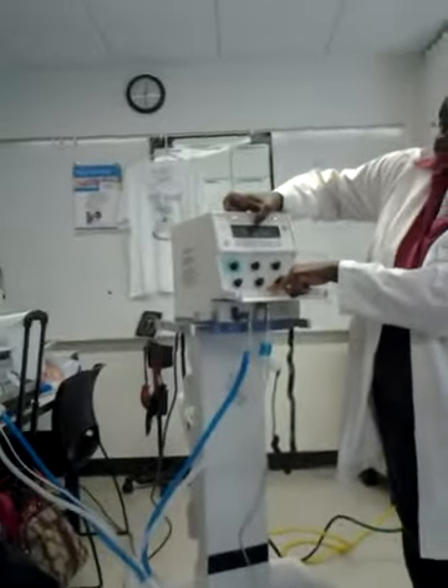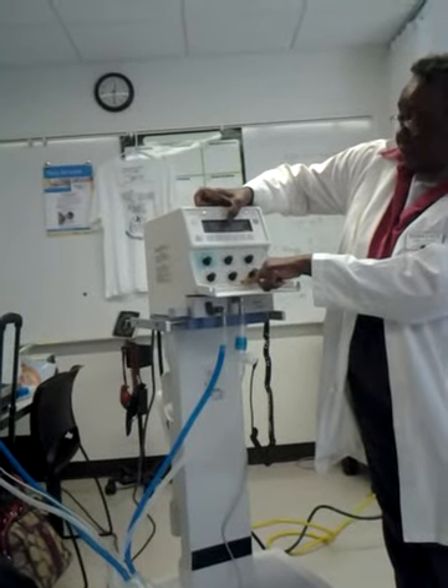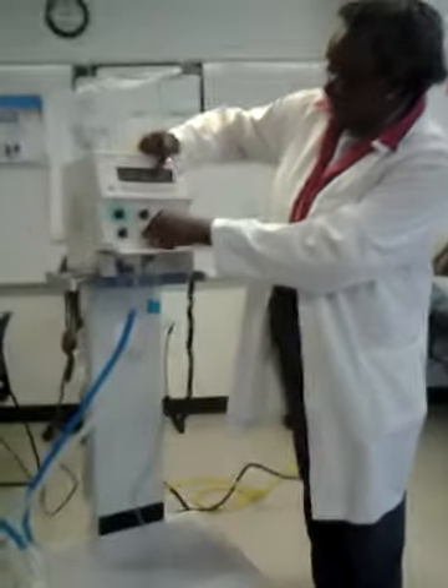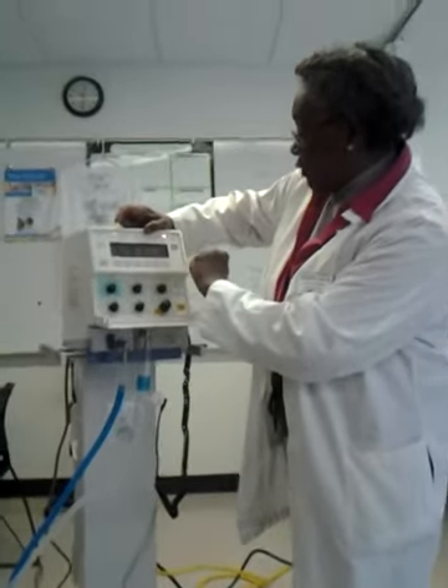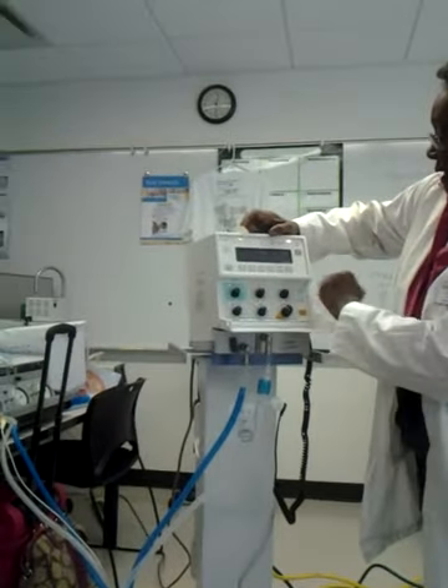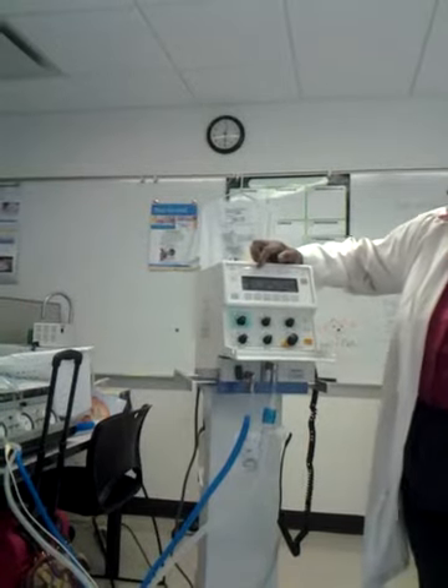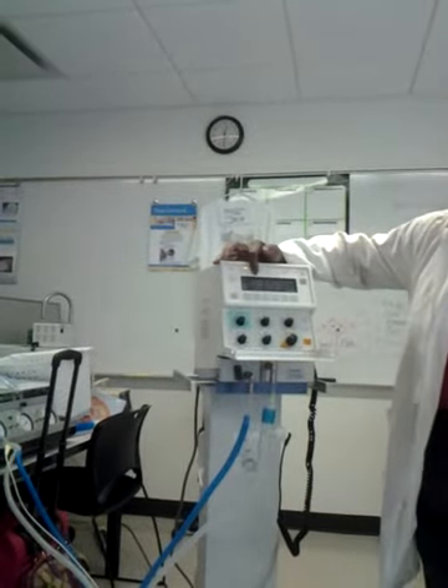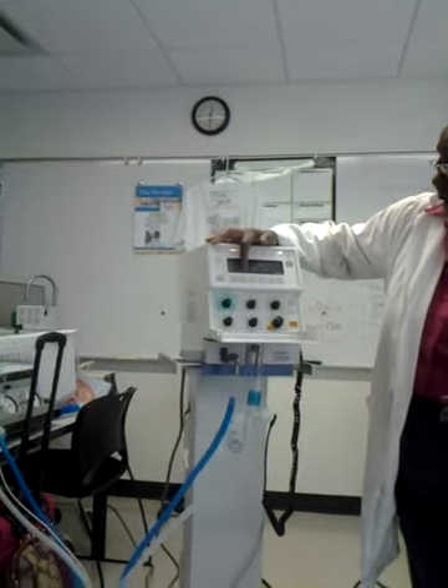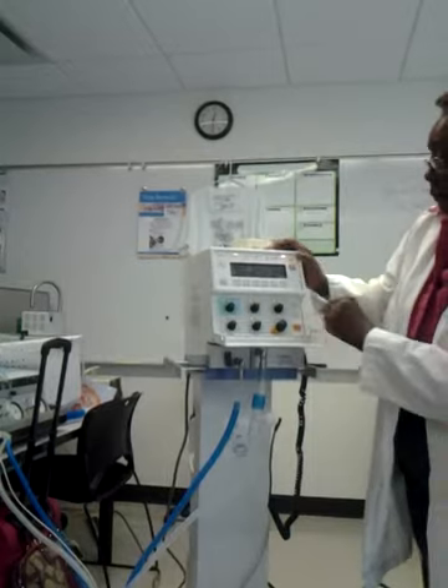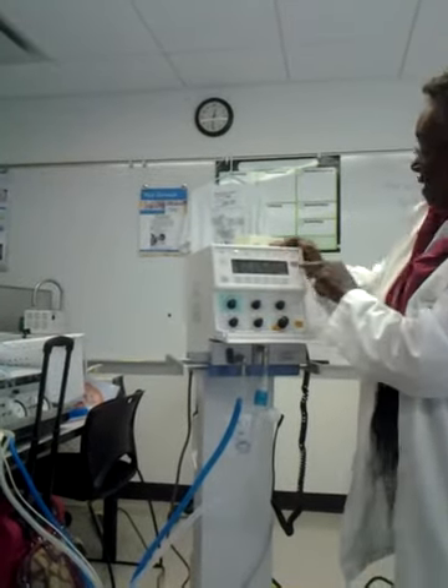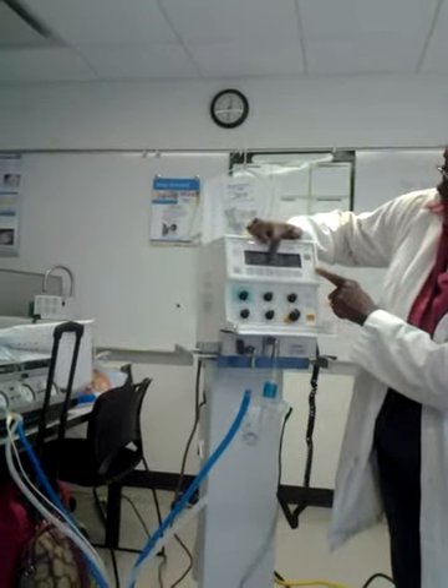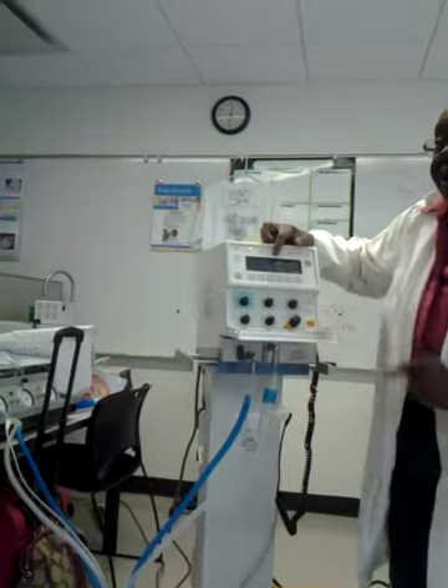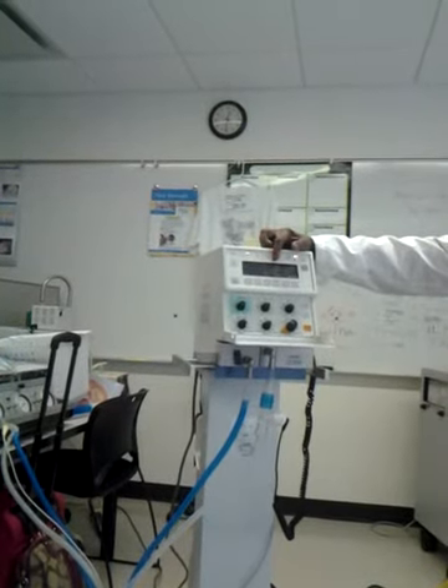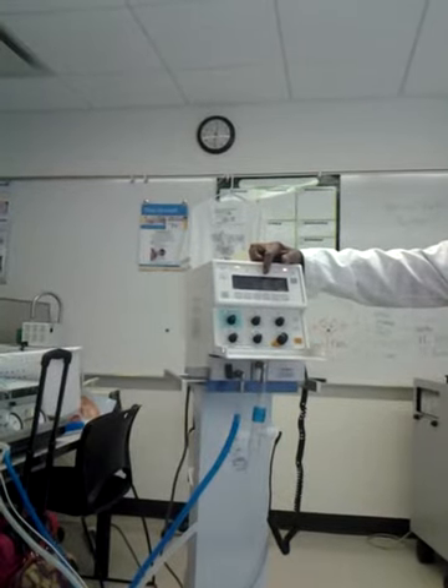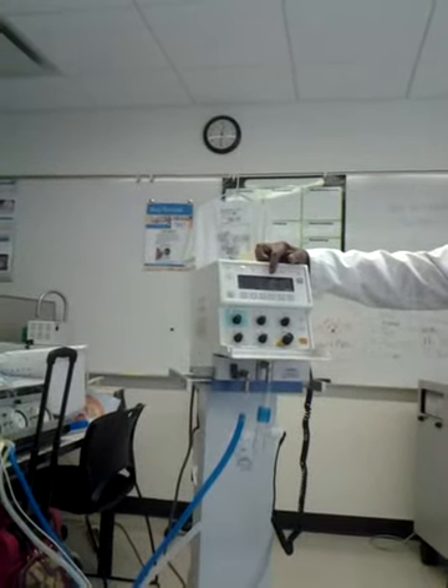And over here, these two numbers, you have your inspiratory flow, your expiratory flow, and your inspiratory pressure. It says 37 centimeters of water. And you also have your trigger set. If I go to this screen, where it says measurement 1, it's measuring my peak inspiratory pressure. It would have my FiO2 if I had one in here, frequency total, it's giving me my minute ventilation and my tidal volume, and if there's any leak in the system. This one actually does compliance measurement. It gives you your static and your dynamic compliance and your resistance for the infant if you're going to be doing all of those different measurements.